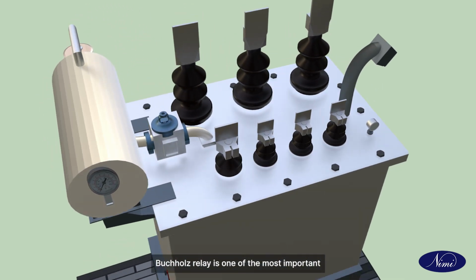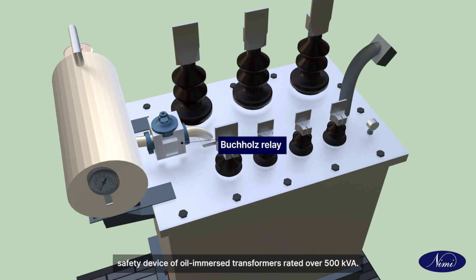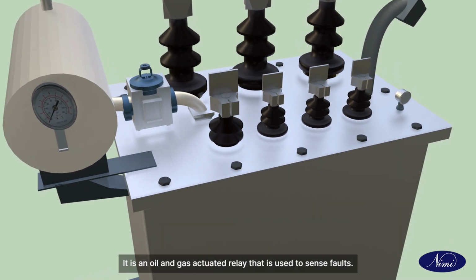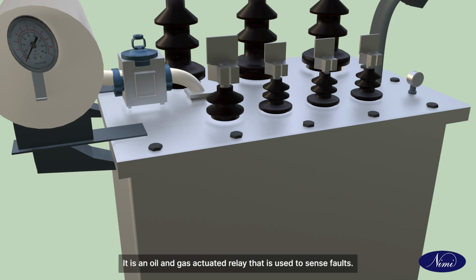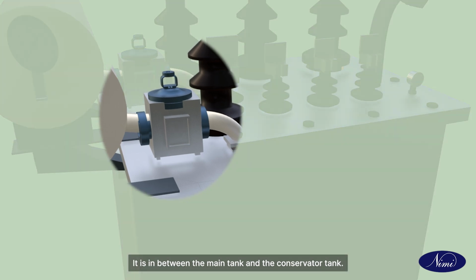Buchholz relay is one of the most important safety devices of oil immersed transformers rated over 500 kVA. It is an oil and gas actuated relay that is used to sense faults occurring in parts immersed in the oil, such as interturn faults, short circuit faults, etc. It is in between the main tank and the conservator tank.